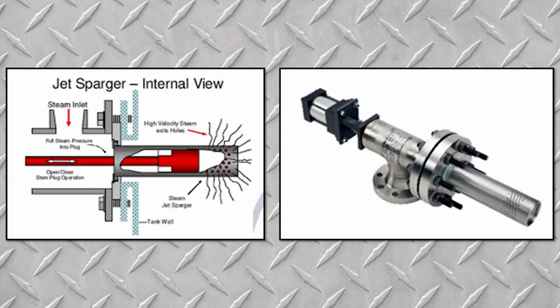Additionally, we have the potential of direct steam injection to warm without the use of a heat exchanger by simply injecting the water with the steam. Its only purpose is to heat, but we consume the steam through this process, which is known as sparging. It's a low pressure steam application, and we'd probably have a pressure reduction valve before the sparger so that we could limit the amount of flow going into whatever we're trying to heat with the steam. However, it's a very efficient way to get high temperature water.